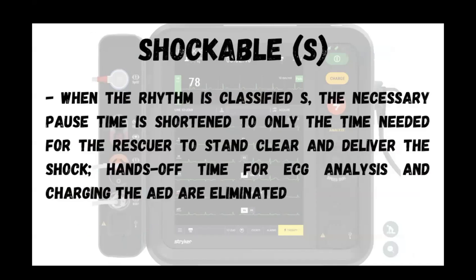What are the three prompts it gives you? Well, the first is shockable. When the rhythm is classified as S or shockable, the necessary pause time is shortened to only the time needed for the rescuer to stand clear and deliver the shock. Hands-off time for the ECG analysis and charging the AED are eliminated — it's done in the background, as we've shown in previous videos.